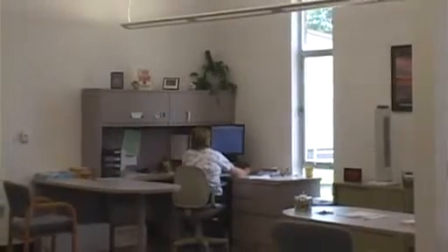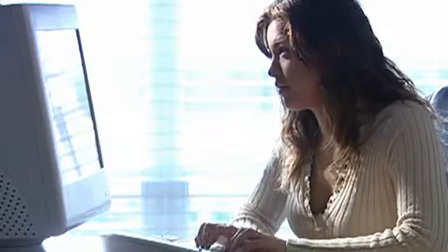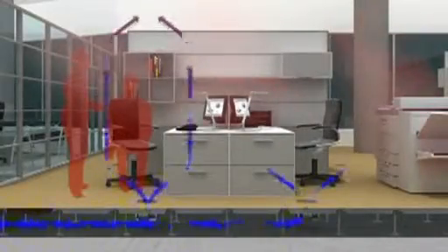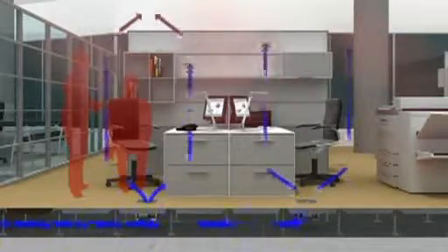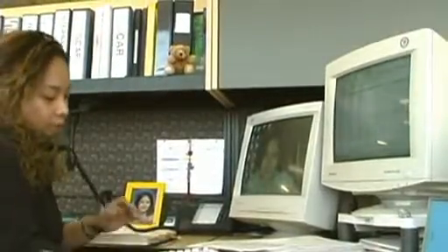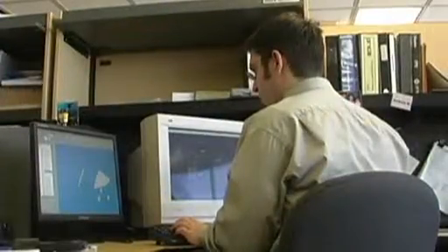People who experience a well-designed underfloor air system consistently comment on how fresh the air in the space seems. This is due to the stratification of stale air and contaminants to the unoccupied zone, while conditioned air is delivered where the people work. And these systems are very quiet. With the lower air velocities and greatly reduced ductwork, noise is simply not an issue. As you have seen, tenant comfort and operability benefits are really quite impressive.